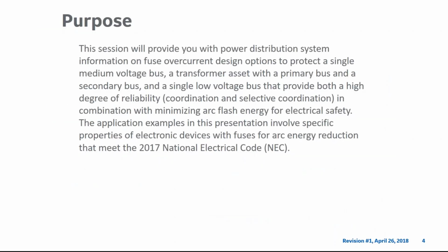Purpose: this session will provide you with power distribution system information on fuse overcurrent design options to protect a single medium voltage bus, a transformer asset with a primary bus and a secondary bus, and a single low voltage bus that provides both a high degree of reliability, coordination, and selective coordination in combination with minimizing arc flash energy for electrical safety. The application examples in this presentation involve specific properties of electronic devices with fuses for arc energy reduction that meet the 2017 National Electrical Code.